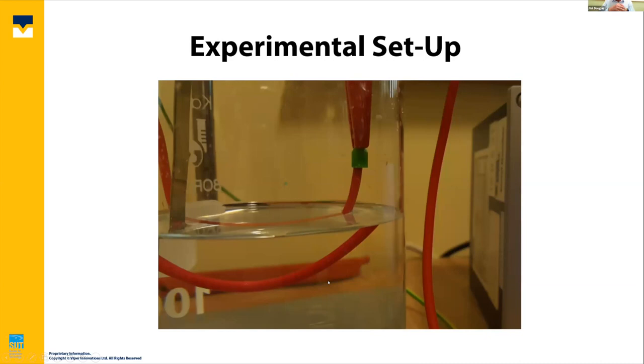So we have set up, and this looks a very simple experiment. It is. What I have done here is put, you can see, a piece of, I think it was 1.5 square millimetre cross-section area, laboratory wire into a beaker of seawater. There's a steel rod in the beaker of seawater, and that represents, if you like, the platform leg or the hull of the FPSO. This cable represents your umbilical or your cable within your umbilical. And what I've done is created a small hole in that cable so that seawater penetrates into the cable.